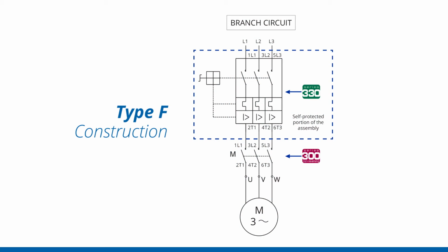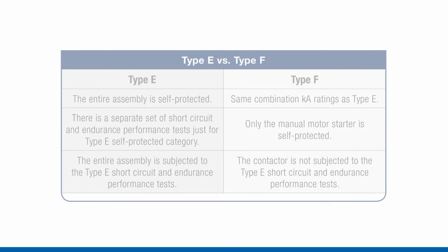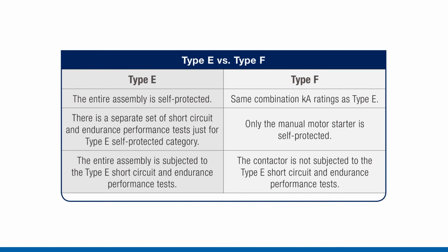The Type F construction is very similar to Type E, except that the contactor is not part of the construction during the self-protected test. So the motor protection circuit breaker, as defined, is self-protected, but the entire assembly is not. However, the assembly is suitable and capable of being applied as a combination motor controller. What that means is that you have the appropriate branch circuit, short circuit, and ground fault protection. However, in the event of a short, the contacts of the contactor could weld. But the device will appropriately clear the fault and protect the persons and equipment from danger. It just may not be immediately operable afterwards.